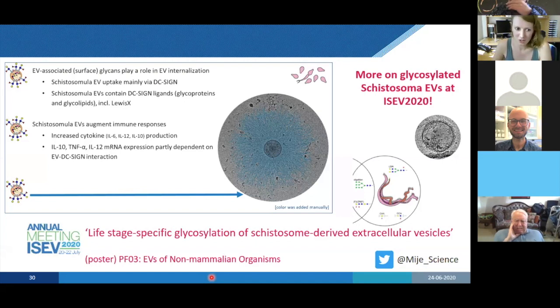But with this isolation, I don't think they are bigger than 800 nanometers, and you do pick them up with NTA. But I must say that what I do with the NTA is that I measure on 3 different camera levels. So also the lower camera levels, so you don't measure the small particles, but more the bigger particles. And then I combine these results and generalize from there. So if you only measure at 1 camera level with the NTA, you're going to miss populations of EVs.